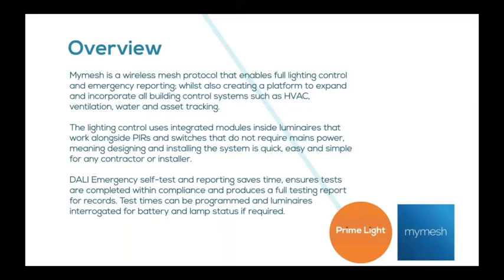On the DALI emergency side, I think this one's quite important, because out there are some other emergency wireless systems, but not necessarily those that incorporate the DALI element. While that gives us our monthly flick tests and yearly 3-hour duration tests, it also allows us to pull back information from the light fitting in the emergency, so we can look at battery status, lamp status, etc. We can also program in times for tests. So if you're doing somewhere like a hospital, where they will not want a 3-hour duration test during the middle of the night, you can program those to happen during the day instead. I think that's a really key feature of the solution.